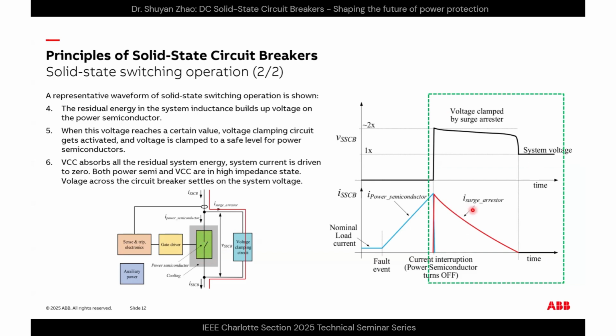It comes to this area, which is called the fault interruption area. Let's say when our main switch, this is the power semiconductor current in this blue waveform, whenever the fault is detected and the trip unit gives a turn off command to the driver of the power semiconductor device, the power semiconductor current will drop very quickly, because typically those semiconductors can turn off the current in microseconds or even faster, in the nanosecond or tens of nanosecond range. So the semiconductor current will drop off very fast, and then the original current that flows through the main switch will be force commutated to the voltage clamping circuit branch.